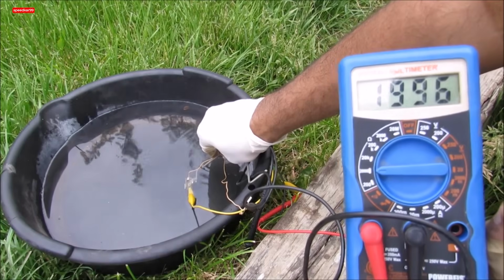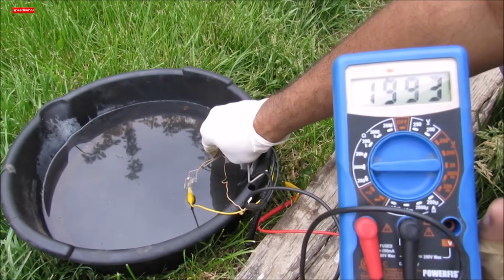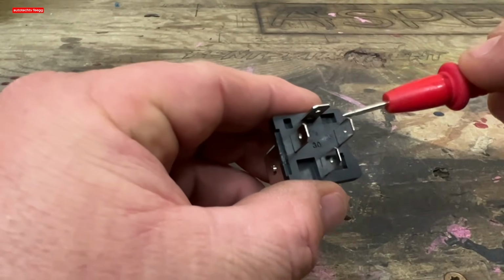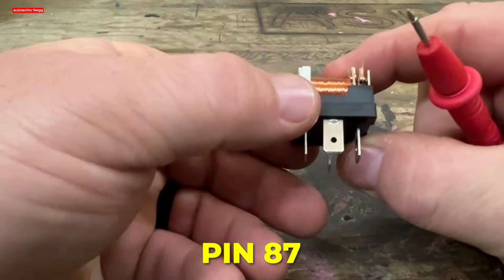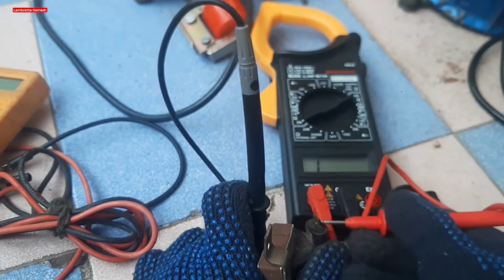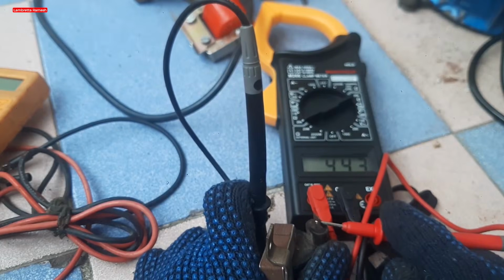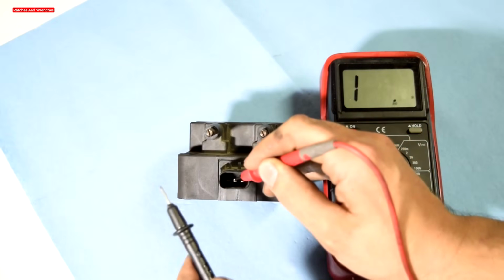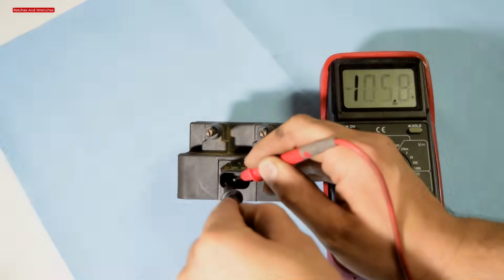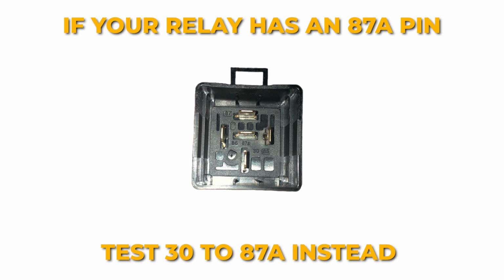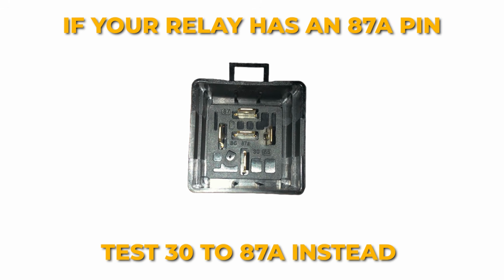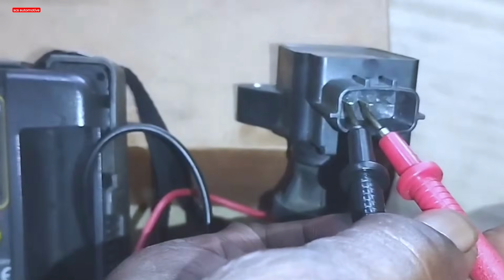Keep the meter on ohms or switch to continuity mode. Touch one probe to pin 30 and the other to pin 87. With no power on the coil, you should read OL or infinity with no beep. Any continuity here means the contacts are stuck closed. If your relay has an 87A pin, test 30 to 87A instead. That pair should show continuity at rest since 87A is normally closed.